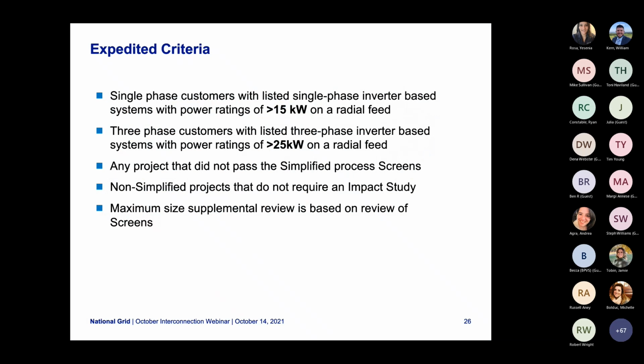My name is Mike Armel, and I am on the ADT team, and I do handle expedited projects. I apologize, I thought I was off mute. So for our expedited criteria, expedited cases would contain single-phase customers with listed single-phase inverter-based systems with power ratings greater than 15 kW on a radial feed, as well as three-phase customers with listed three-phase inverter-based systems with power ratings of greater than 25 kW on a radial feed.